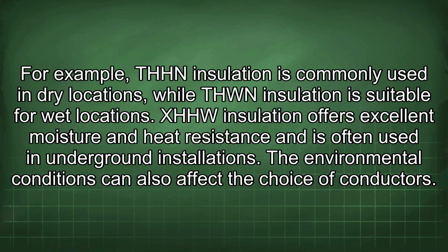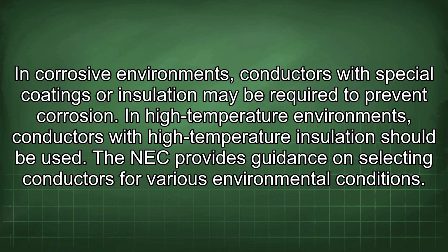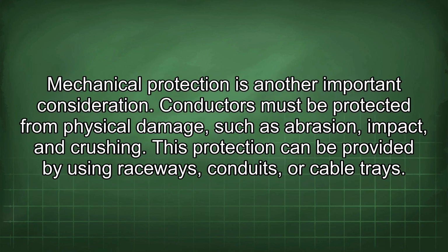The environmental conditions can also affect the choice of conductors. In corrosive environments, conductors with special coatings or insulation may be required to prevent corrosion. In high-temperature environments, conductors with high-temperature insulation should be used. The NEC provides guidance on selecting conductors for various environmental conditions. Mechanical protection is another important consideration.